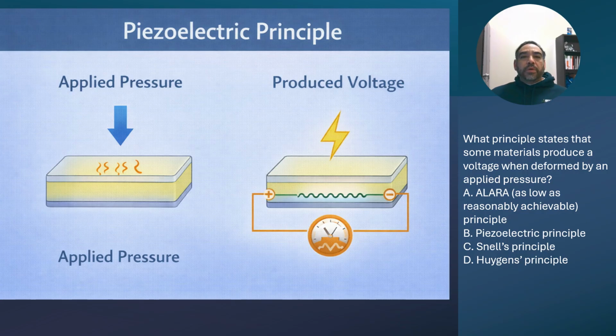The common piezoelectric material is lead zirconate titanate. If we didn't have any piezoelectric effect, you wouldn't have any ultrasound imaging, not modern day. I think some of the earlier devices may have worked differently.